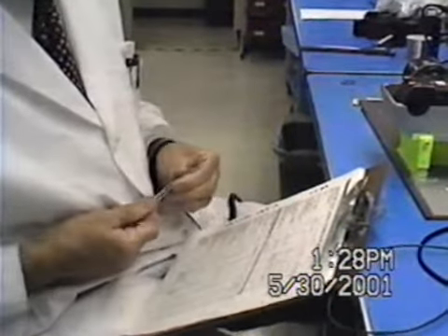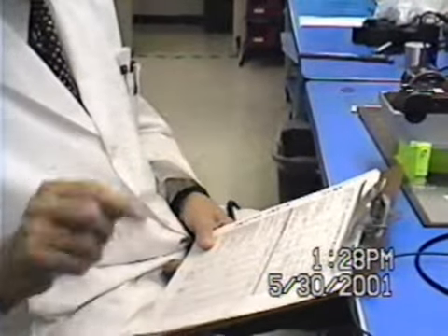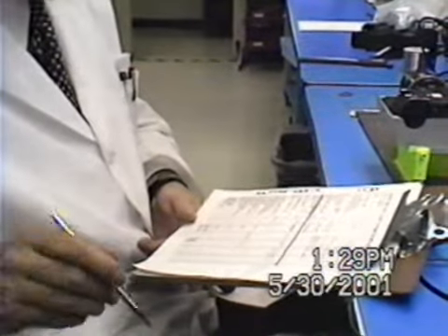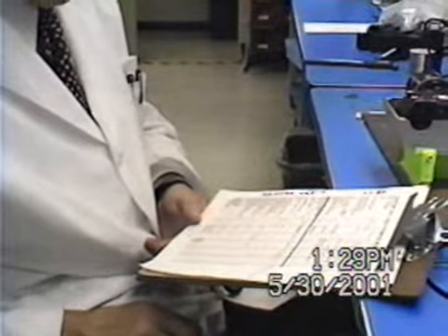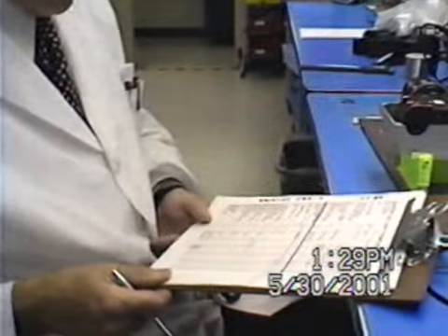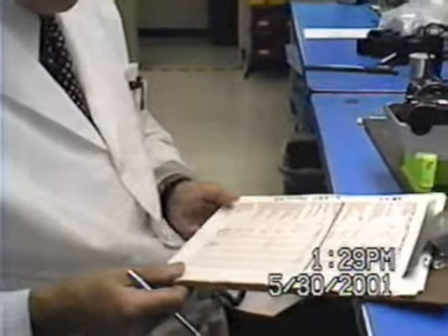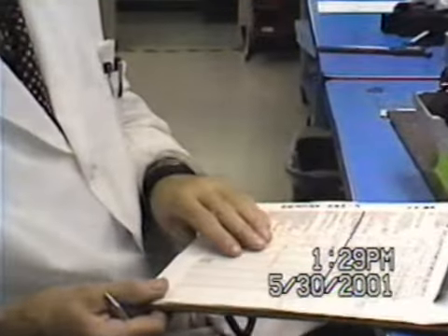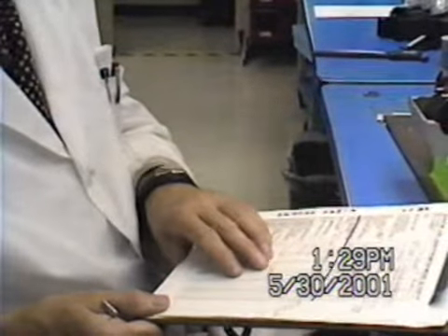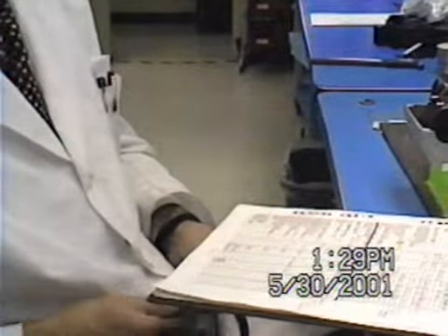So let me say this again. When we changed the resistor R109, which is part of the voltage divider that divides the AC signal down before it goes to the AC amplifier, we changed that dividing resistor, the R109, from 36 to 30K, and now the emissivity, which had been 34, 33 for the white paper, now was 16. And then we adjusted the span to bring it down to 10.